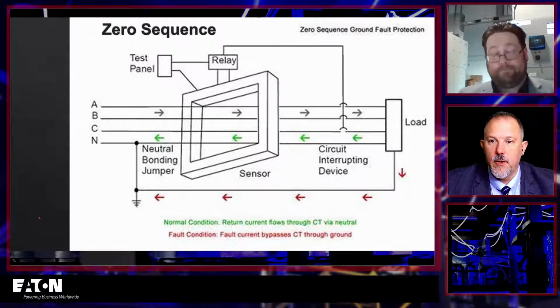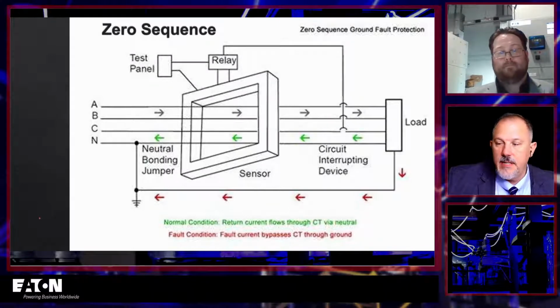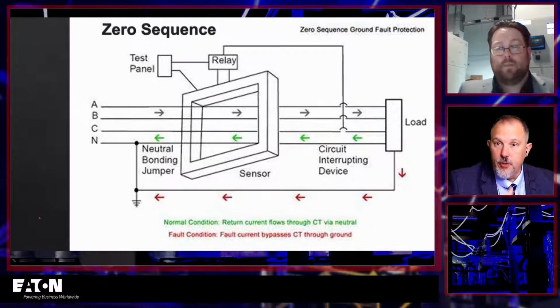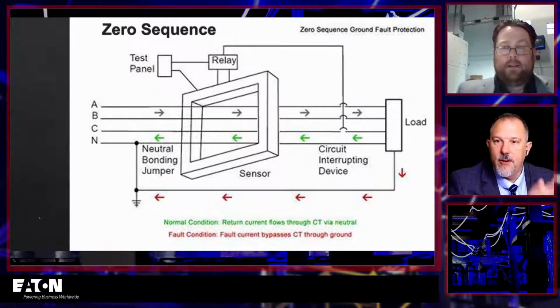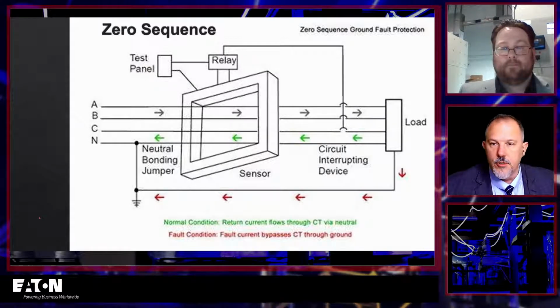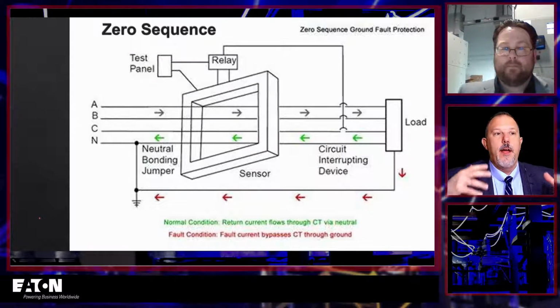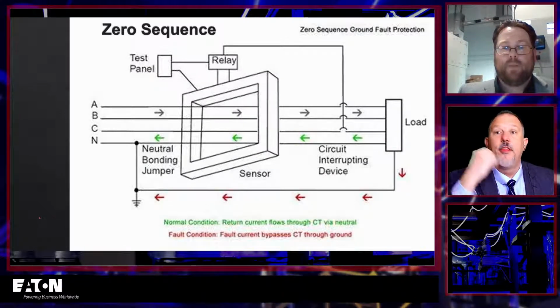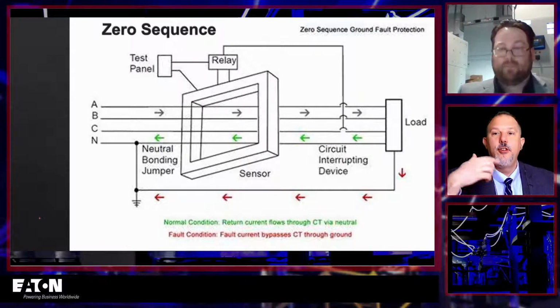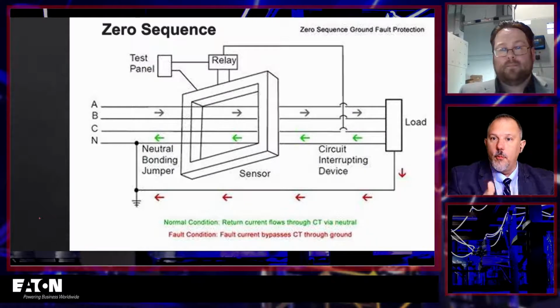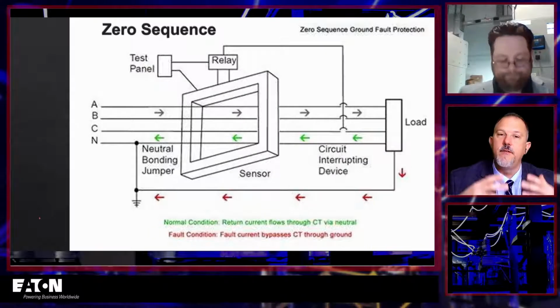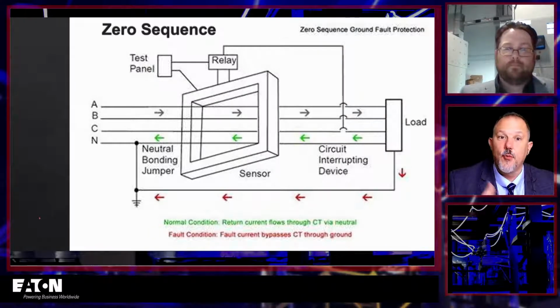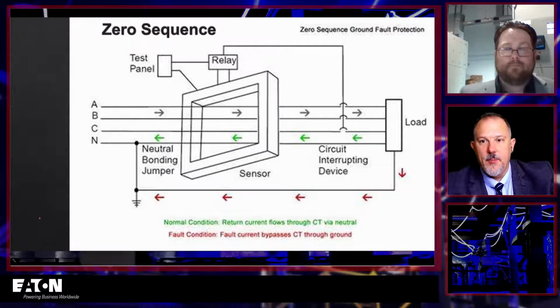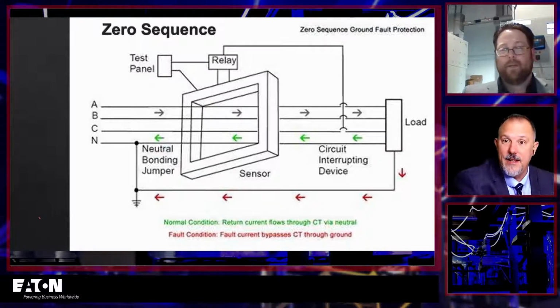Right, because on the installation, you've confirmed the CTs, you've confirmed the wiring, all those jumpers that you talked about, and since it's in there and working and functioning for 3 years or whatever, however long you've got it going, eventually you say, look, I'm going to make sure that the brain is still working in this breaker, and you're going to be testing the basic functionality. You're going to be opening it, closing it, doing all of those functional things from a lubrication perspective and all of that. You don't necessarily have to reprove that the CTs on the bus have the CT ratio that you need and are the right polarity because you've already done that when it was first installed.